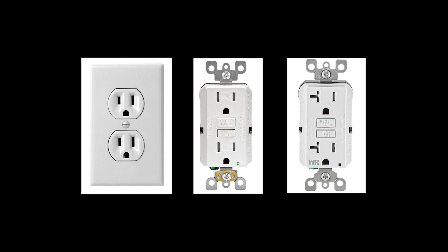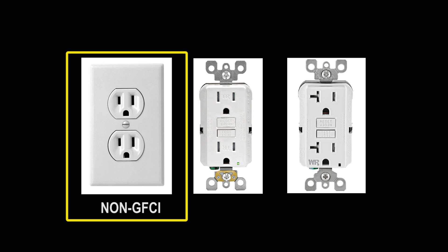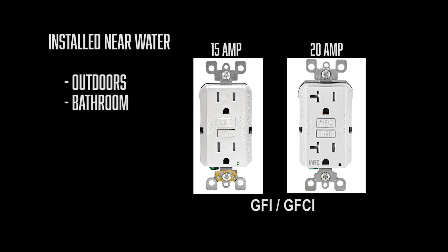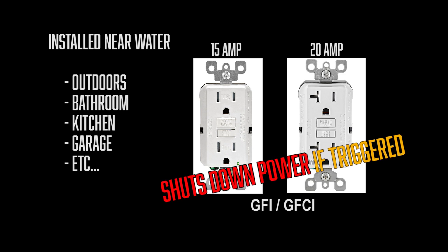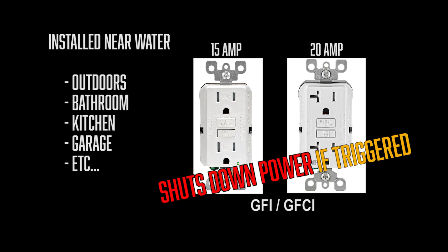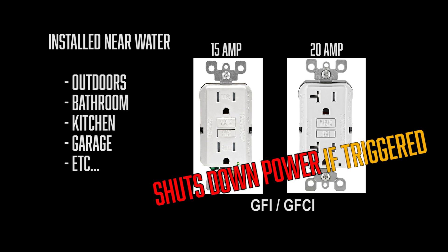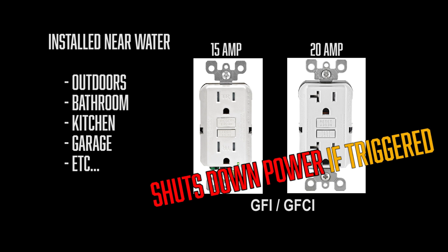Let's compare the types of outlets you can encounter: GFCI versus non-GFCI. GFI, also referred to as GFCI, is installed in areas where water can be a danger, places such as the exterior, bathrooms, kitchens. It is important to use a GFCI outlet because if it senses that the electricity is being grounded through anything other than its intended wiring, like a body of a person, the circuit interrupter will cut the flow of voltage to itself and to any other devices down the line. Once the tripping hazard is eliminated, you push in the reset button and you are back in business.